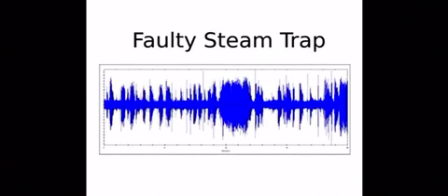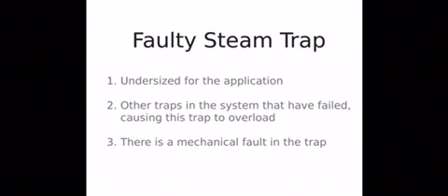Now, look at the dynamic time signal of a steam trap that's not working well. In this visualization, you can see the trap is continuously closing and purging, but the cycle time is way too short. So this trap's functioning poorly, and it could be for any combination of reasons. For instance, the steam trap could be undersized for the application. Well, that's an engineering problem, or is it?